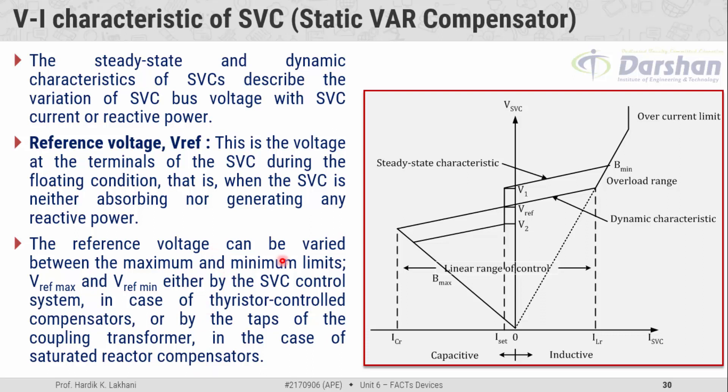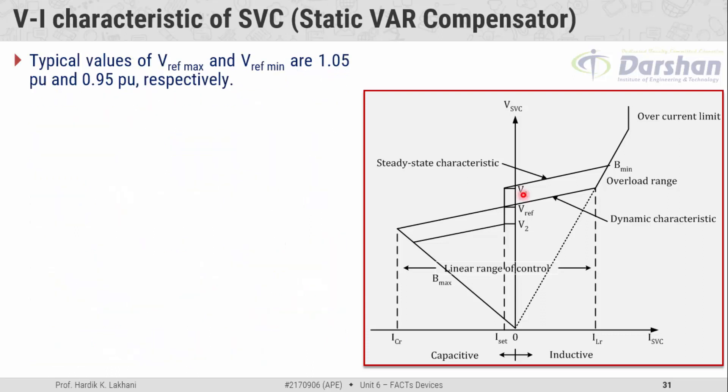There are two ways by which we can change the voltage across the SVC, and it depends on the construction of the SVC. If thyristors are present, then by controlling the firing angle; if thyristors are not present, then by changing the taps of the coupling transformer. In short, the variation in voltage is allowed from 0.95 per unit to a maximum of 1.05 per unit.